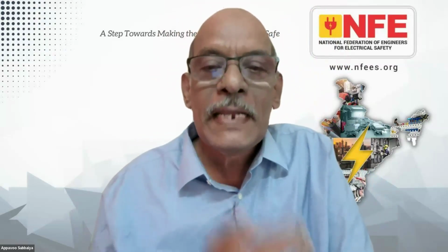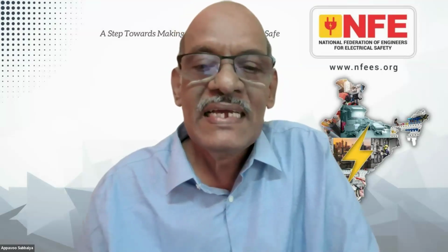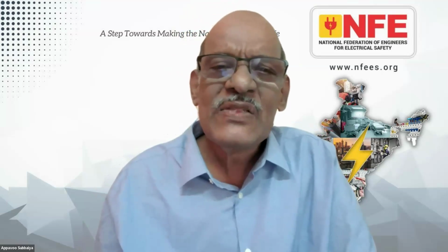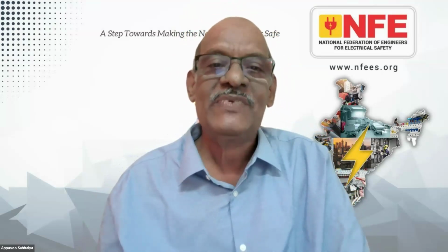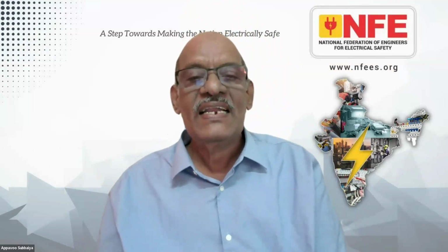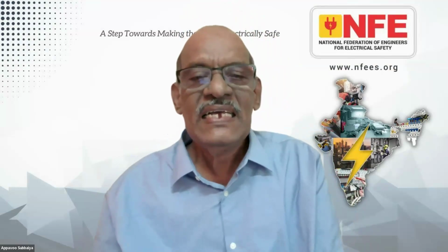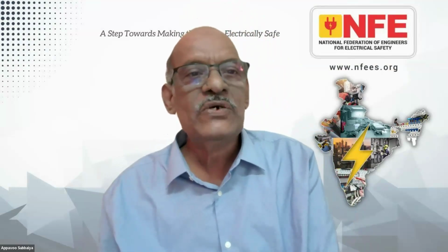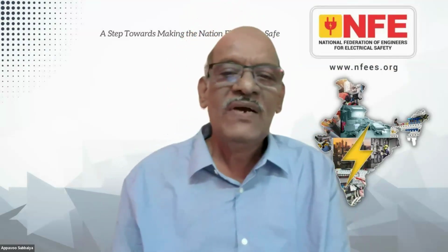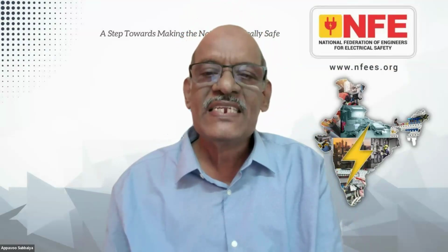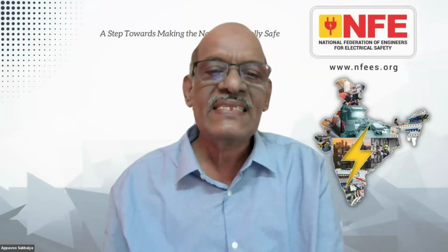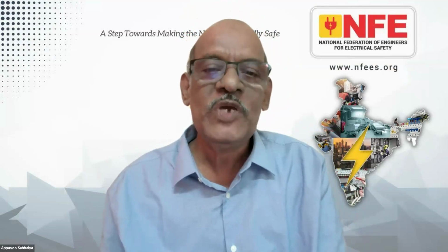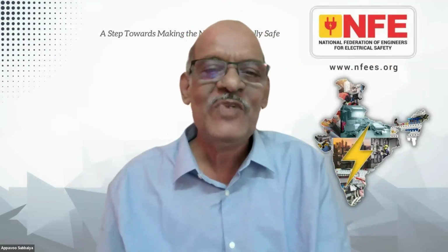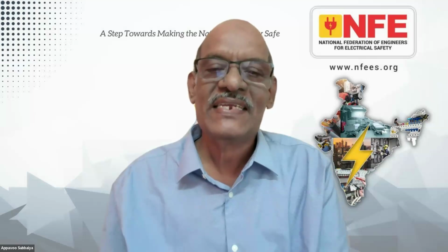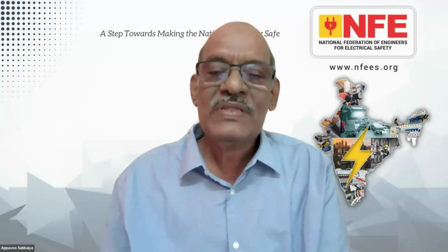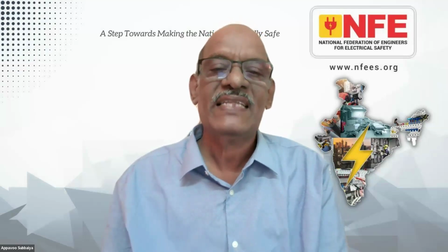See, as already expressed, the earth electrode becomes a concept. Now, earth fault loop impedance is the concept. It is clearly given in Regulation 43. Also, there is a specific provision in IS 3043 under Clauses 23 and 24, where they specify that instead of multiple earth electrodes, a TN-S system is sufficient, and shall be provided with a single point earth connection at the entry. So the fault loop impedance is the criterion, not the earth electrode.